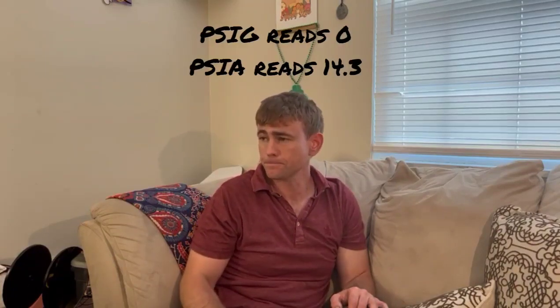So if I was holding a pressure sensor right now and it was a PSI-G sensor and I was just holding it up in the air, I would read 0 PSI. If it was a PSI-A sensor, an absolute pressure sensor, which does include atmospheric pressure, it's reading that on top of whatever other pressure you have. If I had a PSI-A sensor, it would read 14.3 PSI right now.